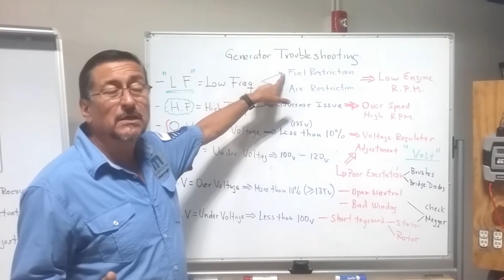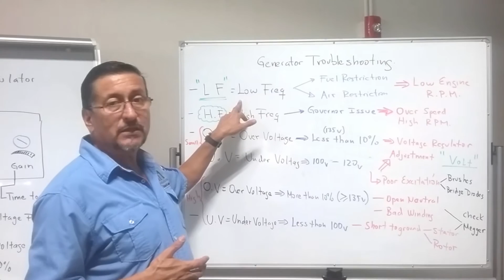Low frequency is basically a fuel restriction or air restriction. Fuel restriction is basically a problem with the fuel filter, fuel contaminated, or fuel lines clogged. Air restriction is basically a problem with the air filter or a problem with the insulation of the sun shield of the generator. Those issues produce basically low engine RPMs. Low engine RPMs are related with low frequency.